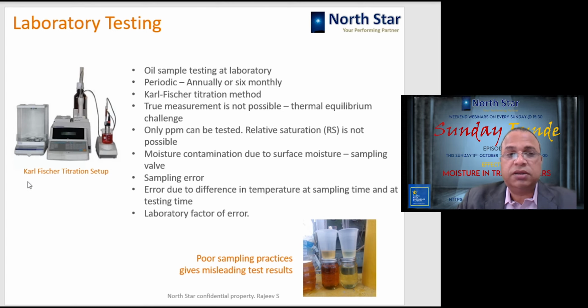Since we are measuring only ppm and thermal equilibrium is not coming into the picture, we have taken the sample from the transformer oil at some temperature. Unfortunately, the situation may be such that the concentration of moisture in the oil is lower and in the paper it is more. Such a sample, when tested, will give you low ppm and you will be happy that my transformer has only 5 ppm.